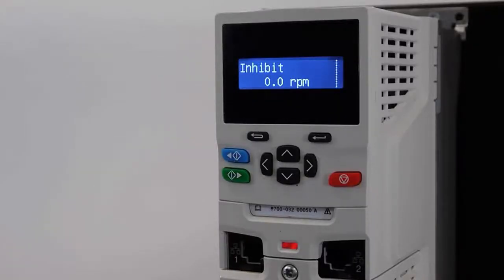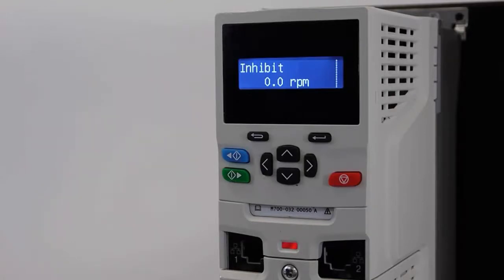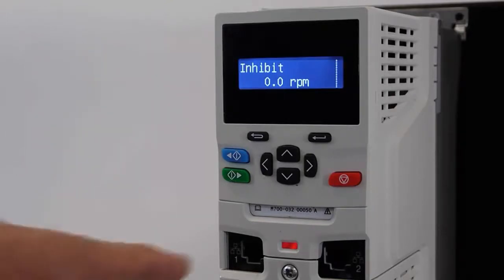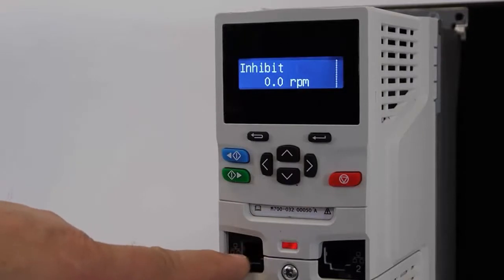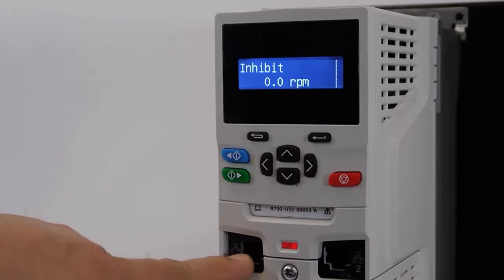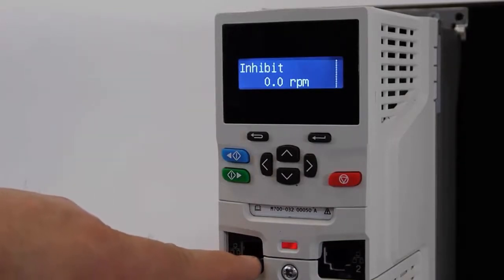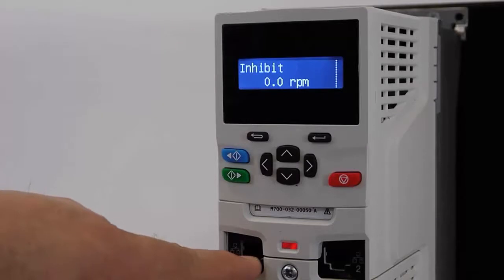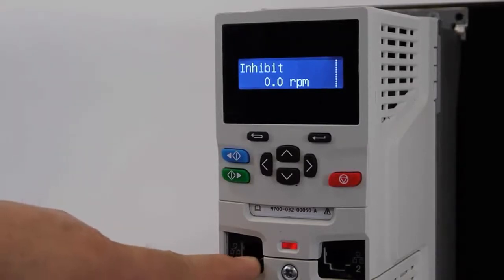I'm going to be configuring an IP address for this Unidrive M700 using the keypad. The Ethernet settings are found in the slot 4 menus, and slot 4 on the M700 and the 702 is this dual port Ethernet switch that you see here. I'm going to be using what's called quick access mode in the keypad to quickly get to the slot 4 menus.